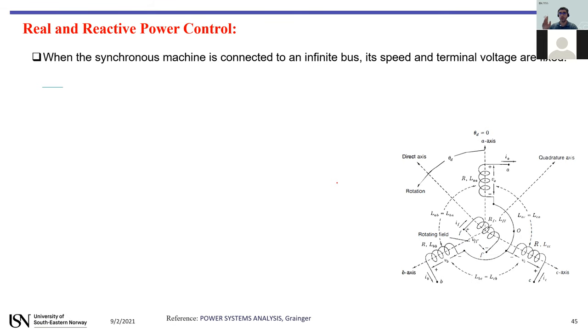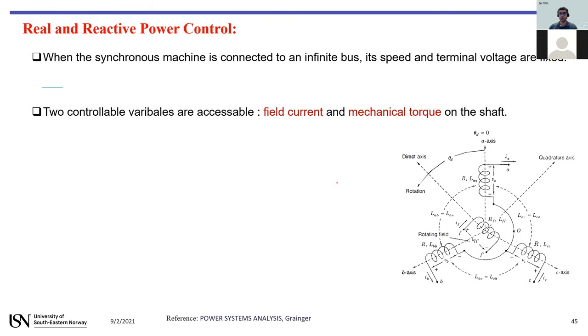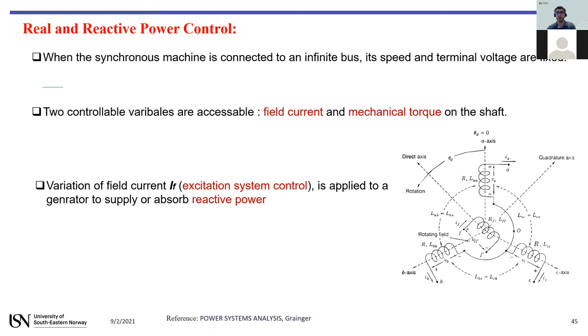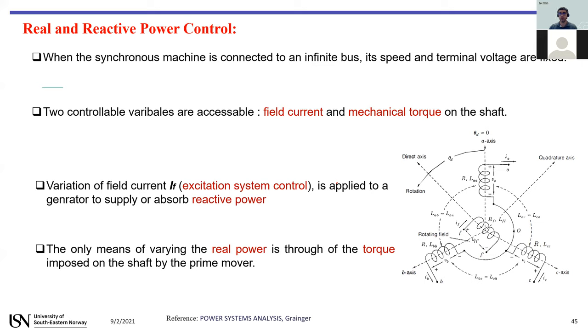Two variables are accessible to us: the field current, which we can change with an external DC source, and the mechanical torque driven by the prime mover. The excitation system control, which changes the field current, is used for reactive power control. On the other hand, if we change the mechanical torque, we can control active power.